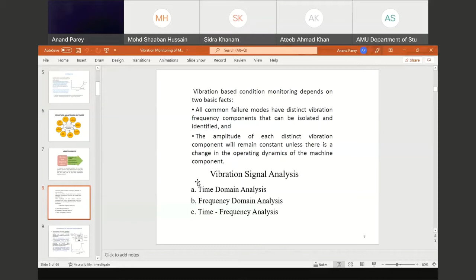If you observe frequency and amplitude, you can know the condition of the machine or whether some fault has developed. Mostly time domain analysis, frequency domain, or time-frequency analysis is done for condition monitoring using vibration. This discussion is mainly focusing on vibration - how you measure the vibration is also important.